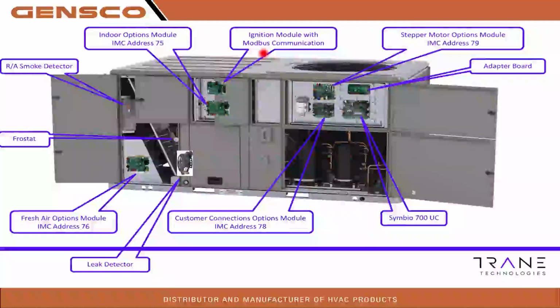And then the ignition module is a single board. So if you have a gas pack, you're going to have the IGN ignition control. Here's our main Symbio control board. You will always have a Symbio control board and the adapter board right above it. These are for accessories that we very rarely see up here in the Northwest, for reheat systems and whatnot for DHU. Here's our new mitigation refrigerant leak detector. Again, I'll show better pictures of this.